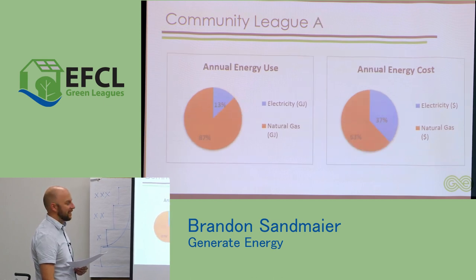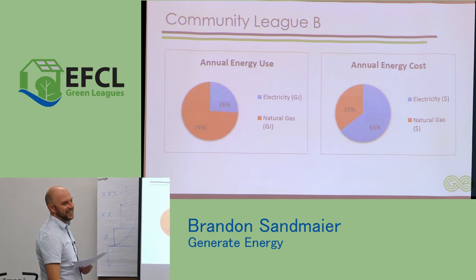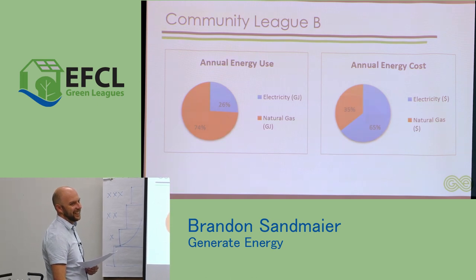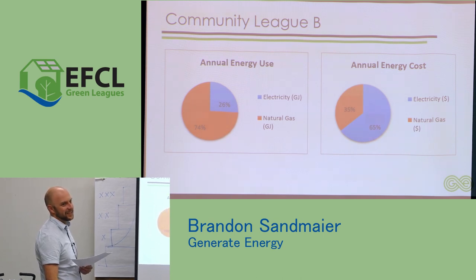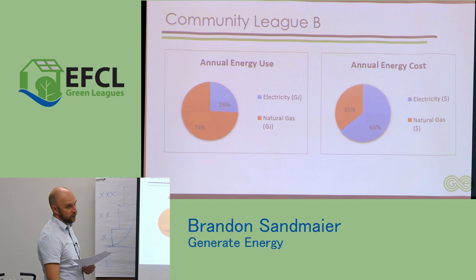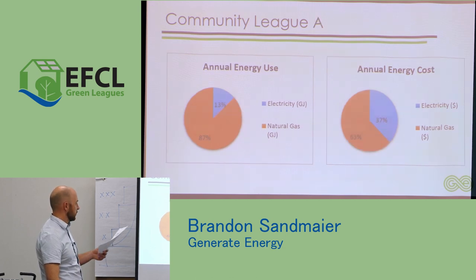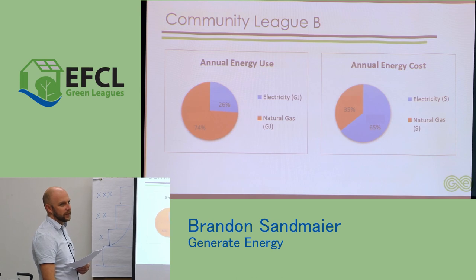13% of their usage is electricity, but it's what, 30 or 40% of what's being paid. There you go. So that indicates the difference, right? So if you can get rid of electric heat or reduce it, that's. Yeah, so this is what I mean by just a bill analysis. We can say, okay, I bet you we're going to find electric heat in this building.